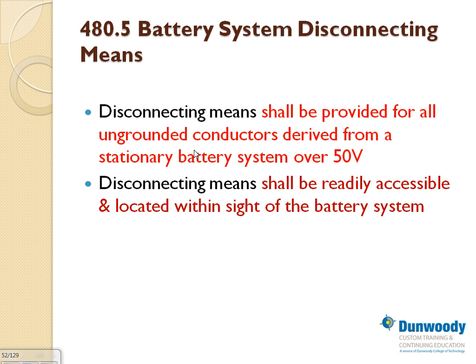You have to have a disconnect to disconnect the ungrounded conductors from a stationary battery system over 50 volts. So if you have a 660 volt DC system, you have to provide a disconnect for the batteries. The disconnect shall be readily accessible and located within sight of the battery system, but does not have to be in the battery room. You can put it within sight, but not in the battery room. Located within sight of the battery system.